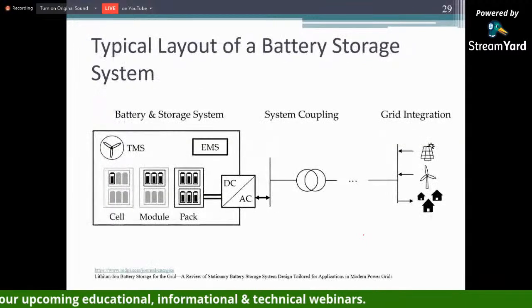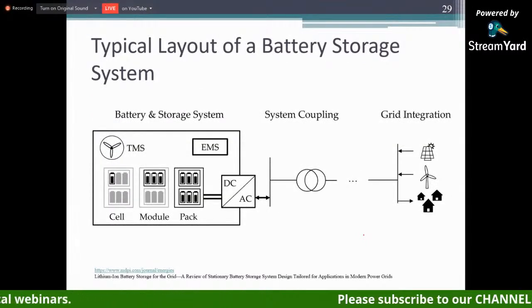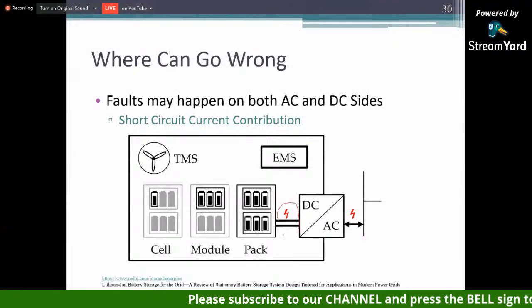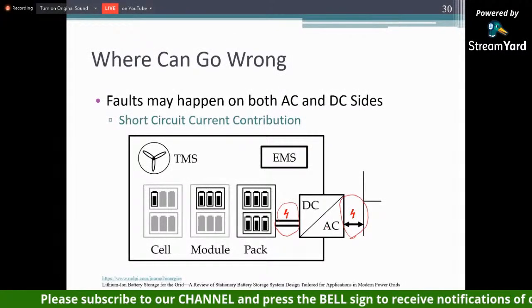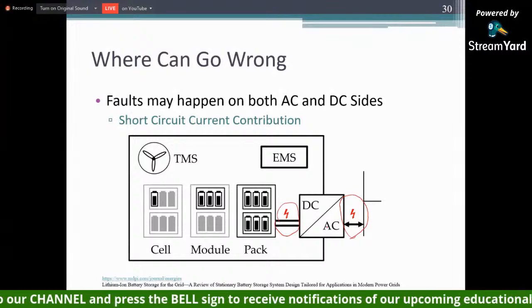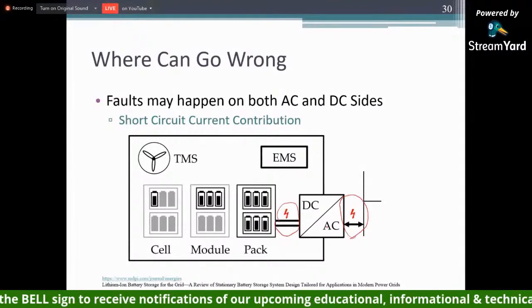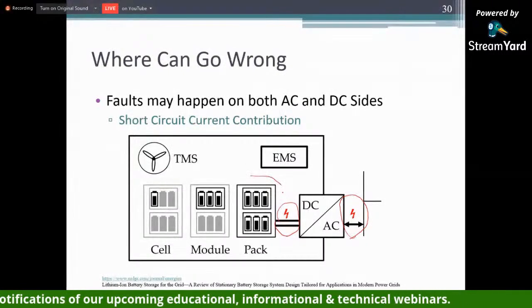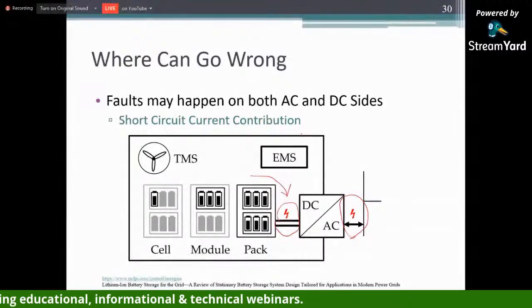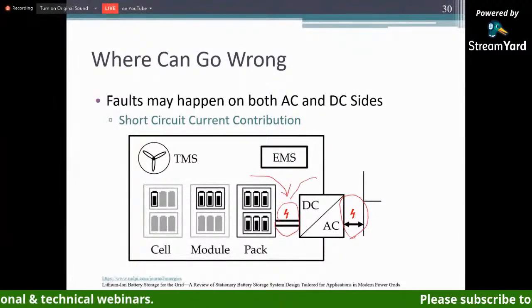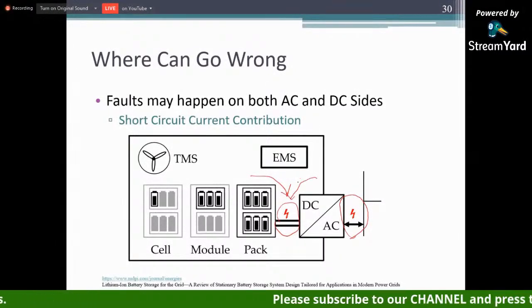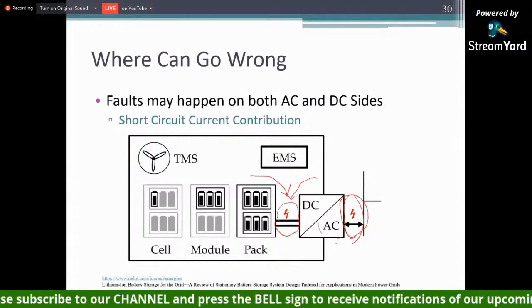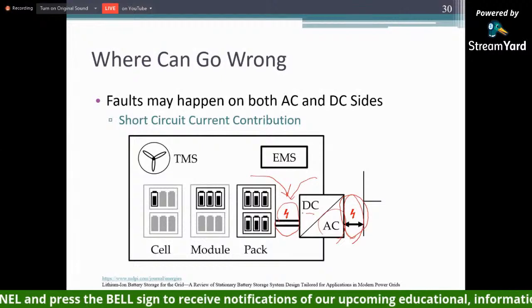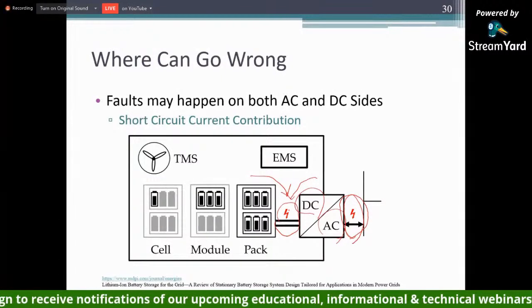For example, if you have a battery system connected to the system, there's a possibility of a fault happening on one side or the other. When a fault happens, you look at what the contribution is from the battery bank or the inverter—normally the inverter has a small contribution. A fault on one side is an AC system, a fault on the other is a DC system, and they have different characteristics.